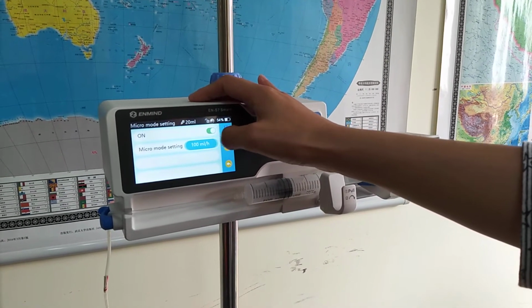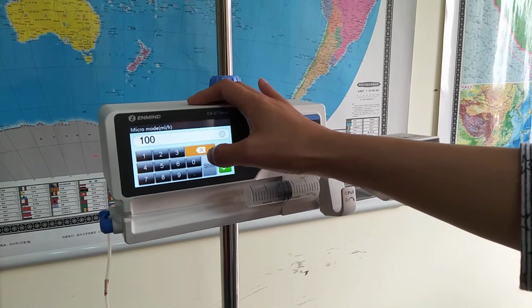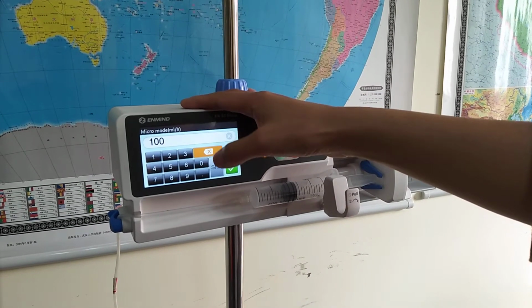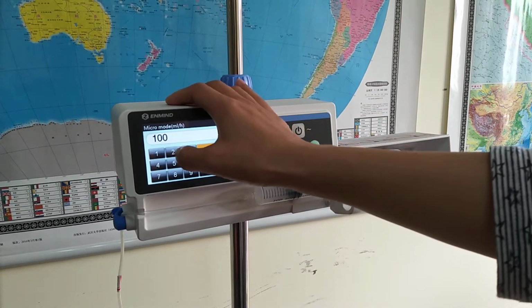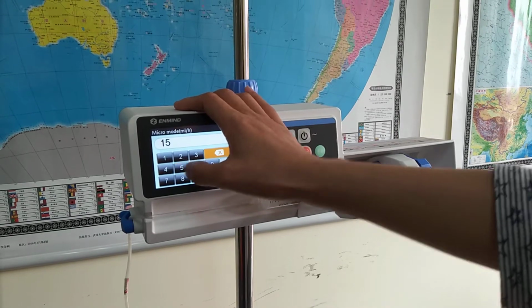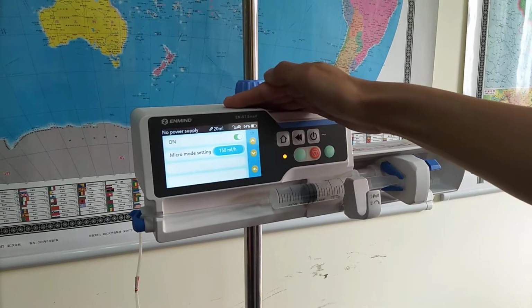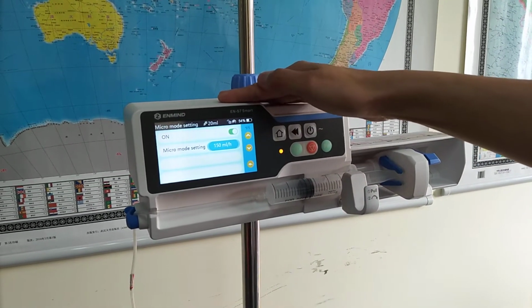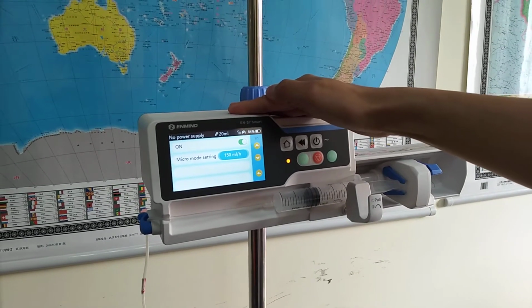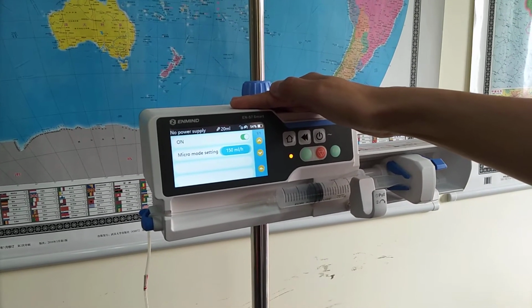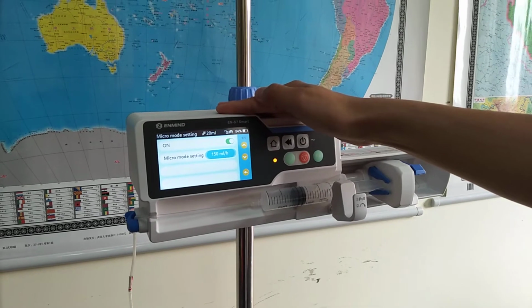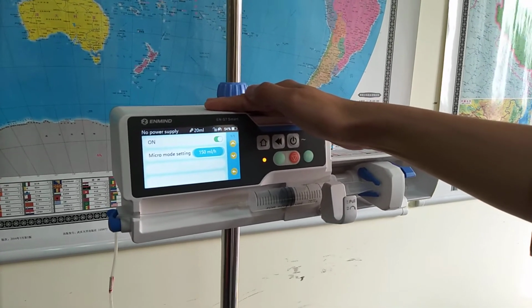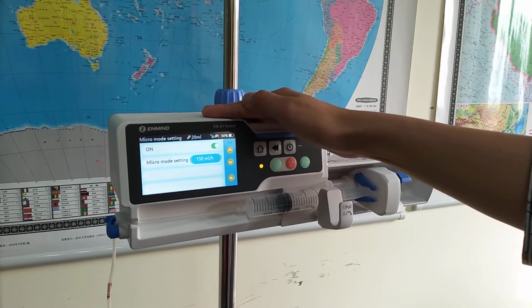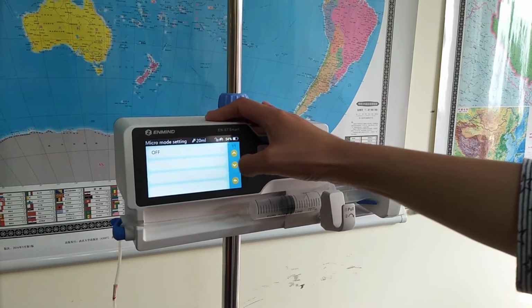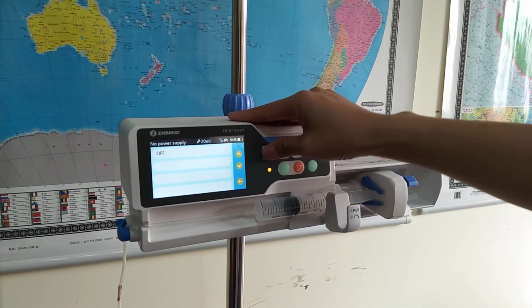So we turn on this mode. We can set up the maximum speed for this mode, like 150. Once we turn on this function, when we go back to the milliliter per hour mode and set up the maximum speed, we can only set up a speed lower than 150. Now let's turn off this function. Click on the home.